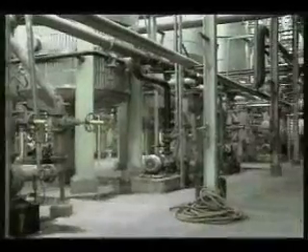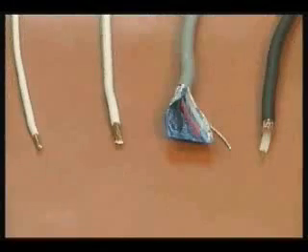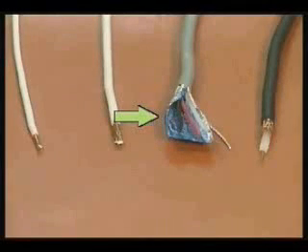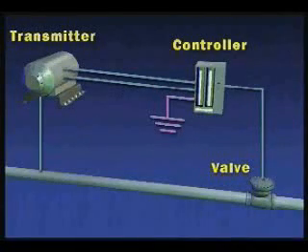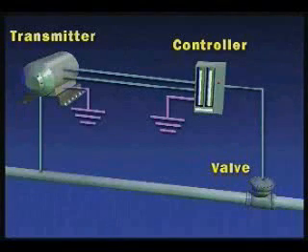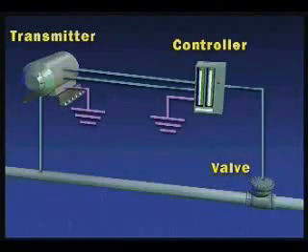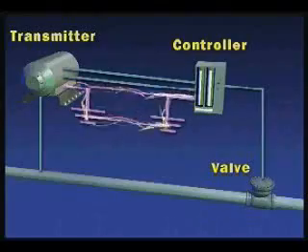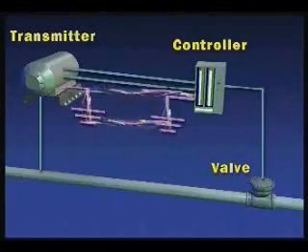Due to the physical layout of the plant's equipment, it is not always practical to avoid all electrical equipment when running signal wires. But it is a good idea to use shielded cable when signal wires pass near high voltage equipment. The shield screens out noise that can affect the signal carried by the conductor. Shielded cables work properly only if they are grounded so that transient current can be drained off before it affects the signal. However, shields must be grounded only at one end or they may create their own source of signal distortion. If a shield is grounded at more than one point, distortion could be caused by a difference in ground voltage potentials. This voltage difference could be large enough to create a current flow through the shield, producing an unintentional ground loop.